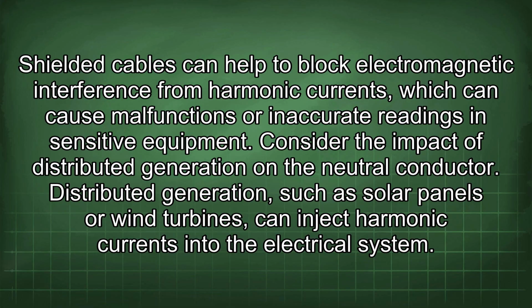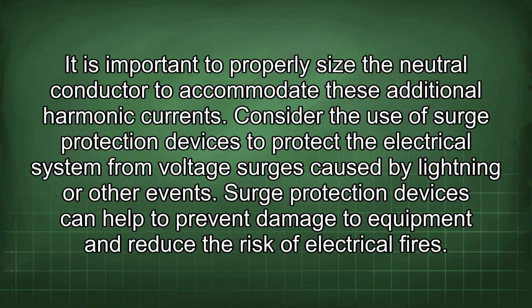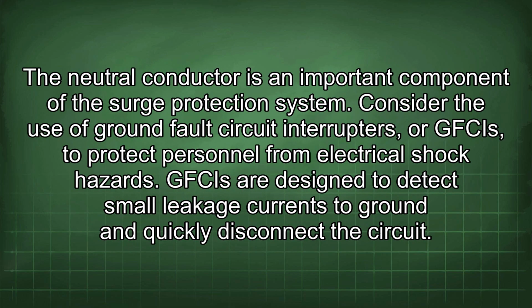Consider the impact of distributed generation on the neutral conductor. Distributed generation, such as solar panels or wind turbines, can inject harmonic currents into the electrical system. It is important to properly size the neutral conductor to accommodate these additional harmonic currents. Consider the use of surge protection devices to protect the electrical system from voltage surges caused by lightning or other events. Surge protection devices can help to prevent damage to equipment and reduce the risk of electrical fires. The neutral conductor is an important component of the surge protection system.